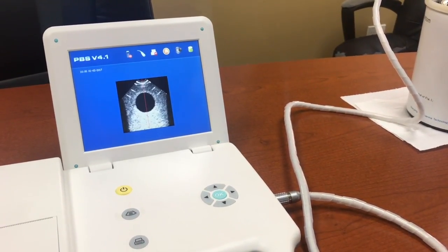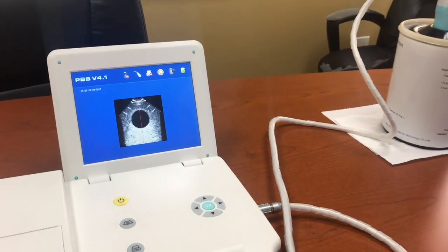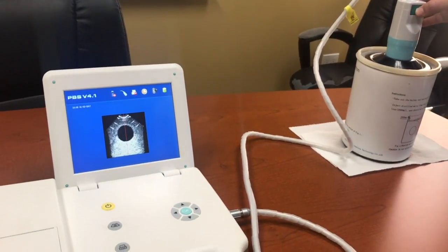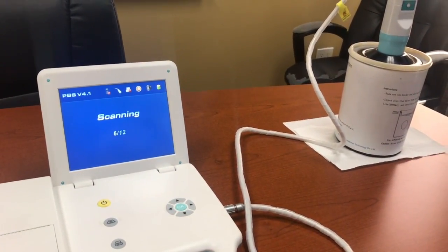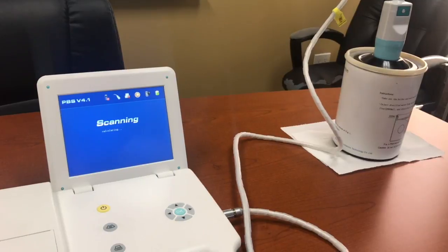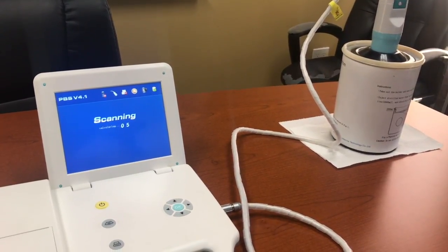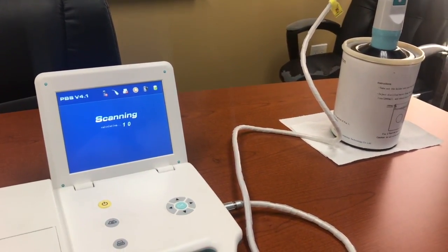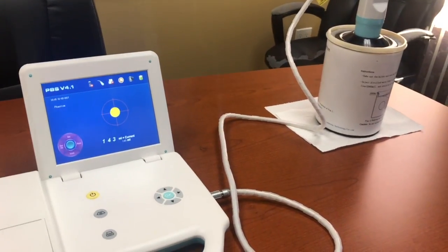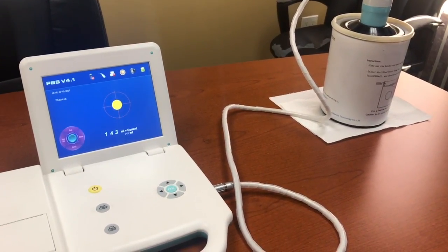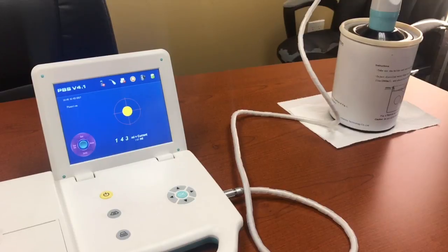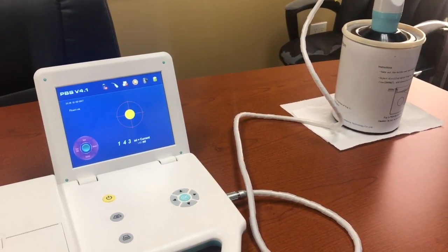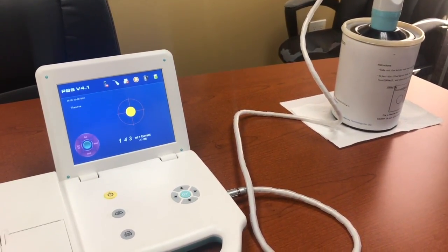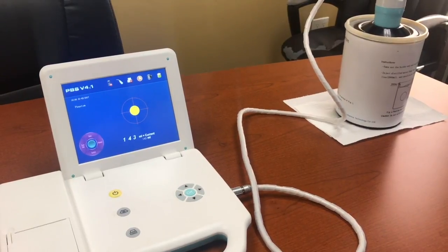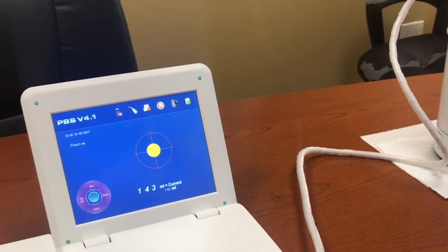At that point, once we feel like we're getting a good scan, I'm going to depress the scan button one more time, and it will actually begin scanning 12 individual slices and then calculating a measurement based on those slices to give a volume of the bladder. In this case, we're reading 143, which is slightly low for this phantom, but well within the 10% allotted margin of error.